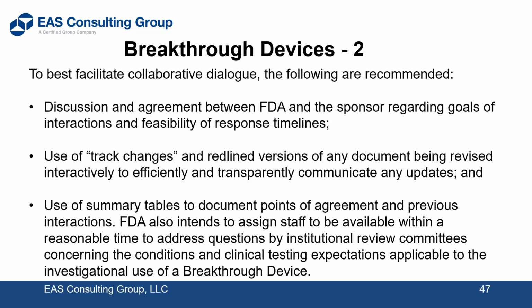So you notice here, some of the things that be subject matter to discuss with the agency. Changes is a big issue with the FDA. That's why design control was implemented in the mid-90s, 820.30. The desire to capture changes because the FDA recognized that in the development phase, R&D was very loosely controlled.